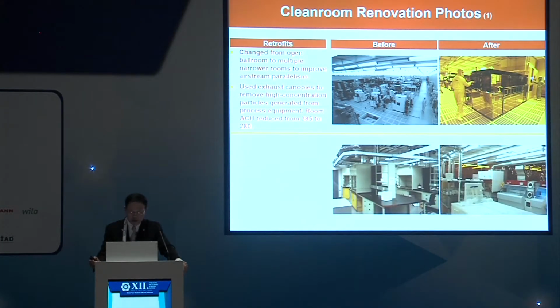And the one below was a university chemical lab. Before was a chemical lab, after renovation, it became a nano research lab, ISO class 3. And it's a 100% HEPA upper ceiling, and uses teardrop lighting, because all the ceiling is occupied by HEPA. There is no place for lighting. So lighting is underneath this 2-inch T-bar. And it's a raised floor return.